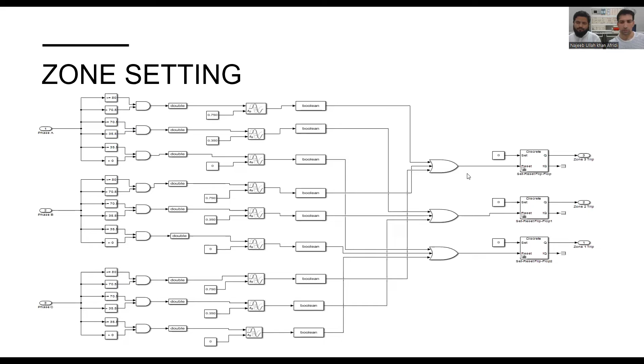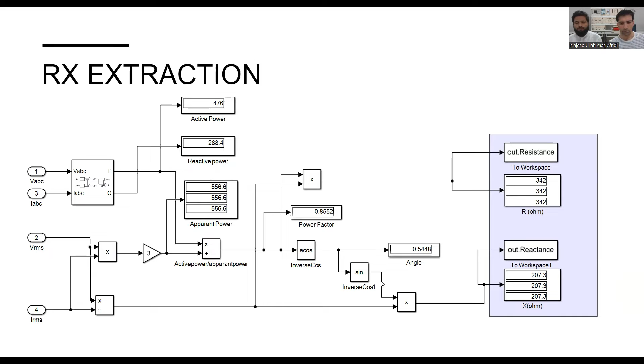In this portion we have extracted the RX diagram, which explains the characteristic of the distance relay. So here we take active power and reactive power, and then we extract apparent power. So we take the active power and apparent power ratio. From here we extract the power factor, and from the power factor we extract reactance and resistance. In this normal condition, as you see, all current is normal, voltage is normal, and the system is operating normally.